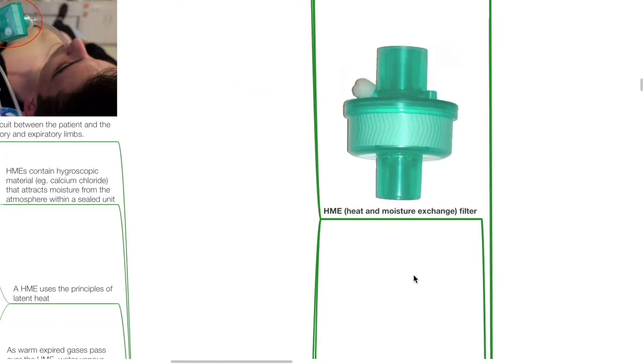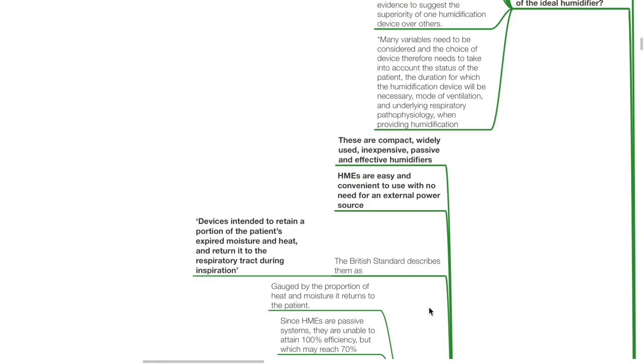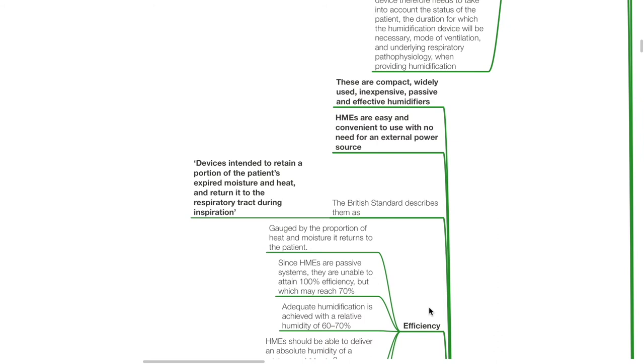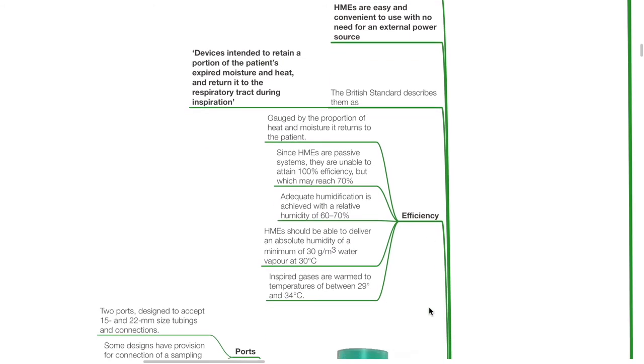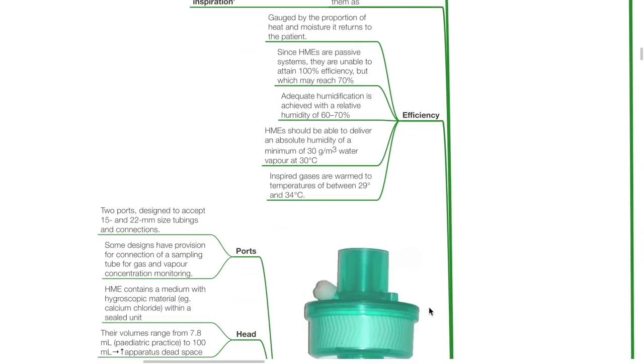The HME (heat and moisture exchange filter). These are compact, widely used, inexpensive, passive and effective humidifiers that are easy and convenient to use with no need for an external power source. The British standard describes them as devices intended to retain a portion of the patient's expired moisture and heat and return it to the respiratory tract during inspiration. Efficiency is gauged by the proportion of heat and moisture returned to the patient. Since HMEs are passive systems, they are unable to attain 100% efficiency but may attain 70% efficiency. Adequate humidification is achieved with a relative humidity of 60–70%, and HMEs should deliver an absolute humidity of a minimum of 30 g/m³ at 30°C. Inspired gases are warmed to between 29–34°C.